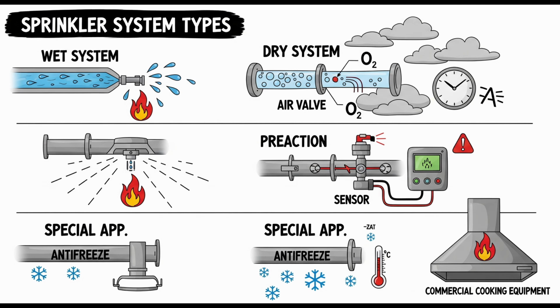One option is to connect the end lines of the two systems at the corner using check valves, arranged so that activating one system also operates one sprinkler just around the corner on the other system's piping. The intermediate pipe connecting the check valves must be arranged to drain properly. A bit complex, linking the systems at the corner. What's the alternative? The alternative is simpler. Just install an additional sprinkler on each system, located strategically right around the corner from the main line. So either connect the systems with check valves and drains, or just add extra sprinkler coverage right at the corner to ensure there are no gaps in protection. Exactly. Seems simpler to just add the extra head usually.